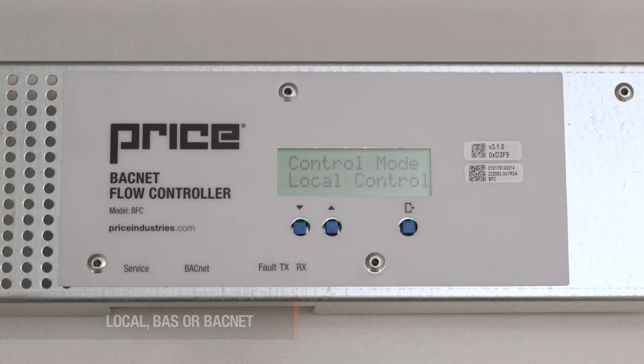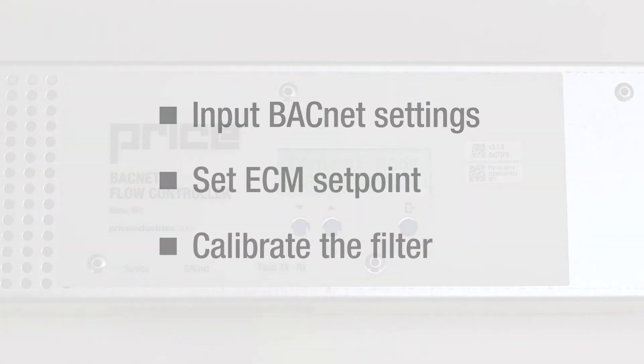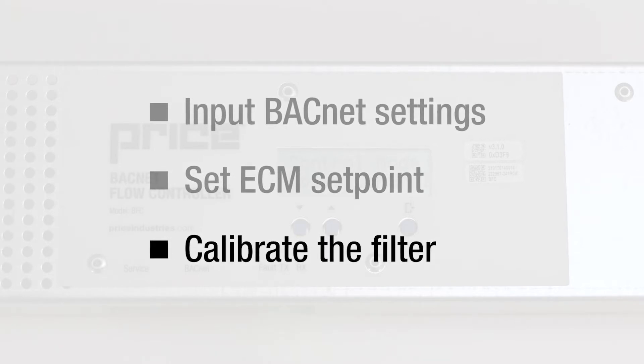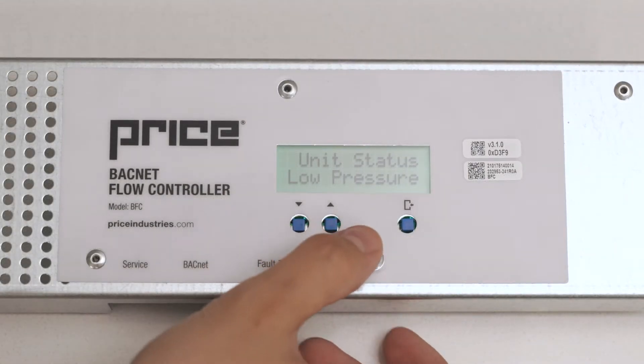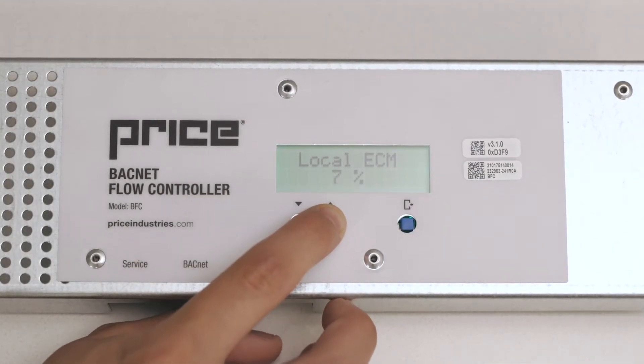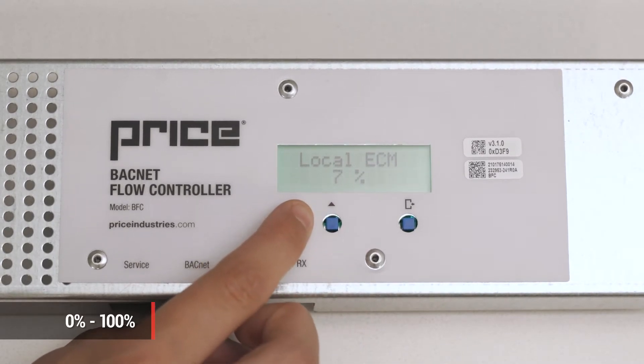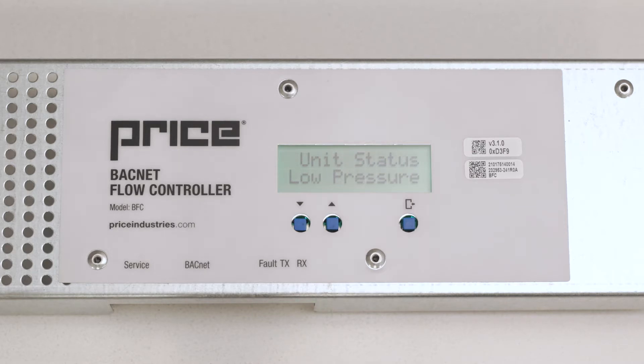On initial setup of the BFC, the following tasks should be completed in this order: input BACnet settings if applicable, set ECM set point, and calibrate the filter. To set the local ECM set point, use the arrow keys to adjust the set point from 0 to 100%. This should be done with the balancing team to confirm airflow rates. This can also be done over BACnet or using a signal from the BAS system.